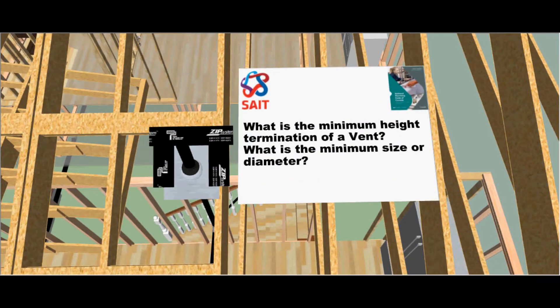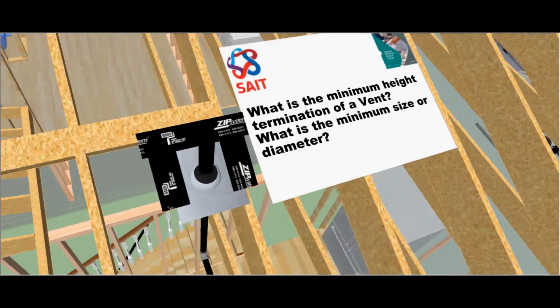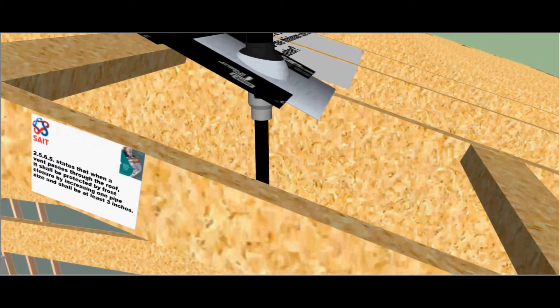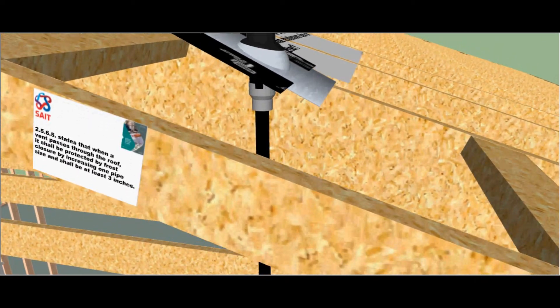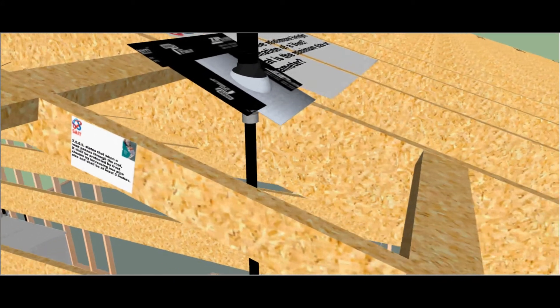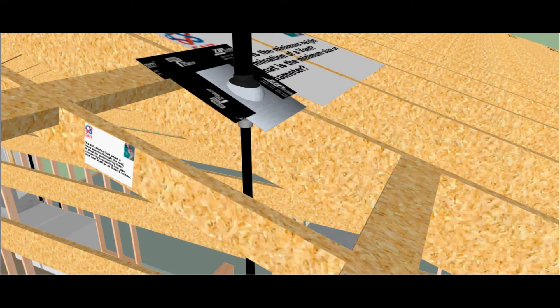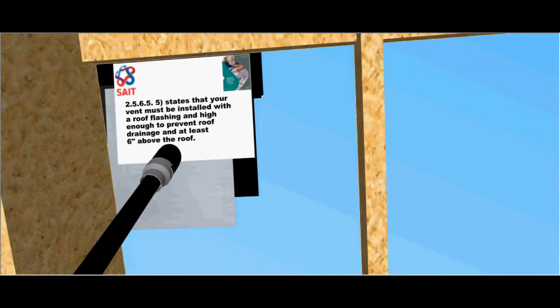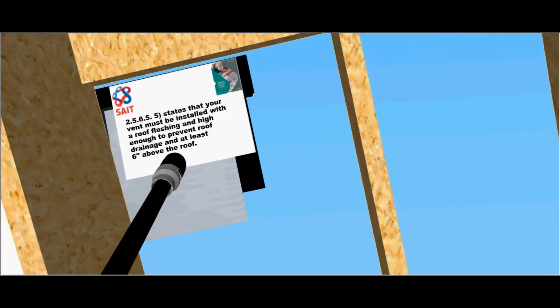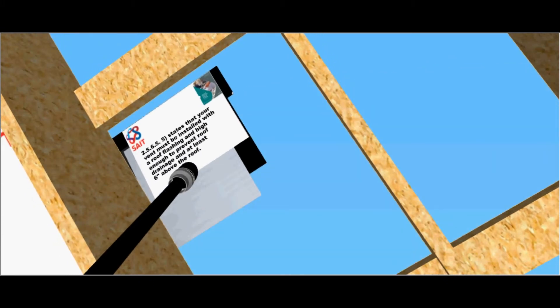What is the minimum height termination of a vent? What is the minimum size? Clause 2565 states that when a vent passes through the roof it shall be protected from frost closure by increasing one pipe size and it shall be at least three inches in diameter. Clause 2565 also states that a vent must be installed with a roof flashing high enough to prevent roof drainage and at least six inches above the roof.